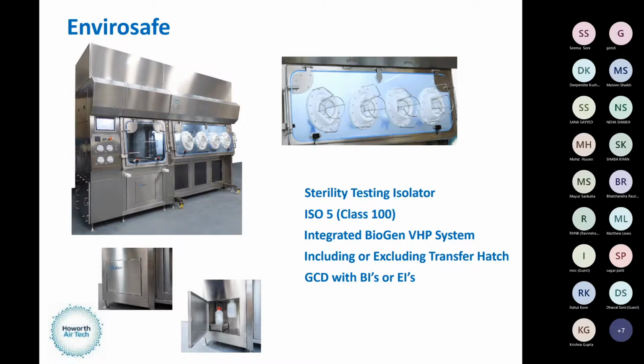The cycle development has traditionally used the biological indicators, but we also have the capability of utilizing enzyme indicators. If you're not familiar with enzyme indicators, this is something maybe would be of interest, because this will give you immediate results. So the machine that's utilized to take the test takes about 10 seconds to give you the result, whereas BIs can take maybe a week and maybe longer.